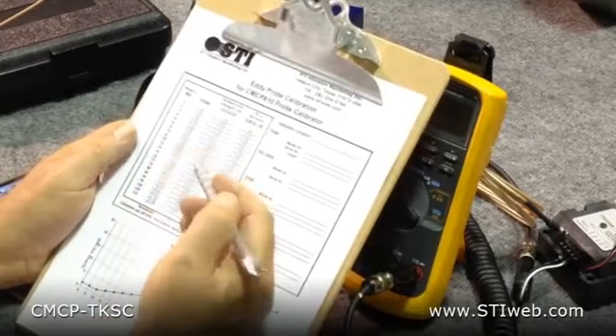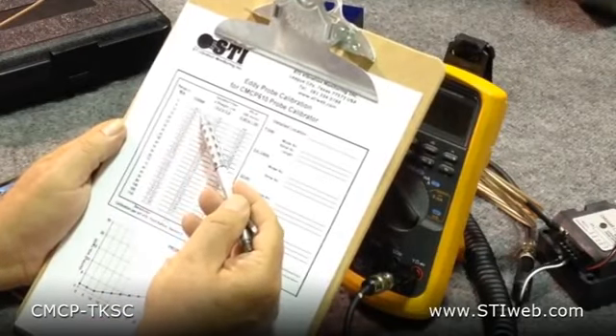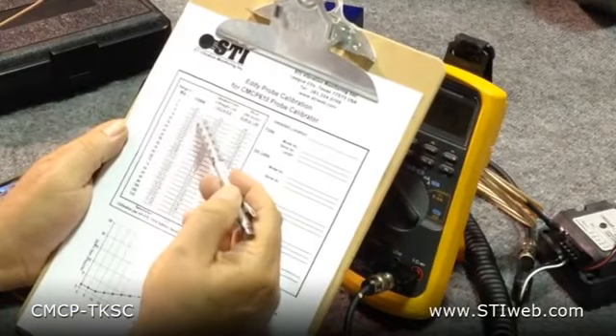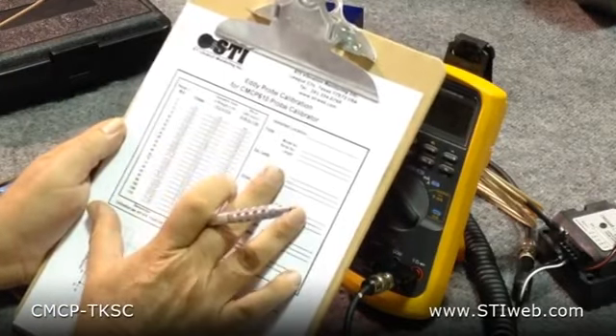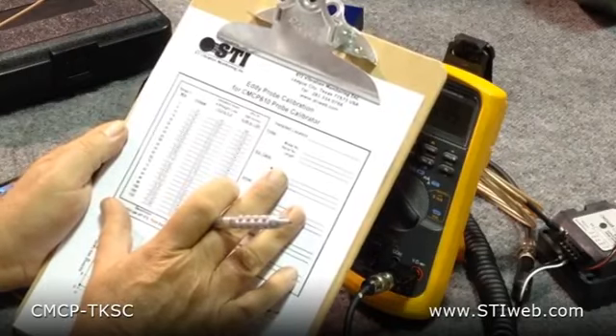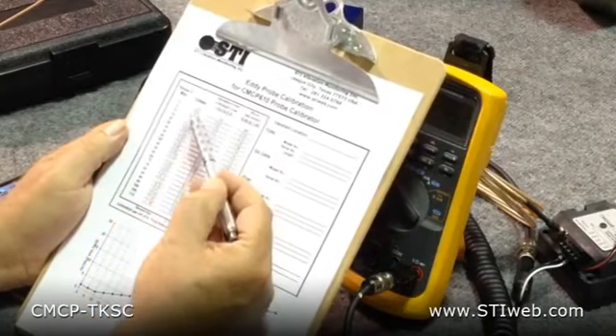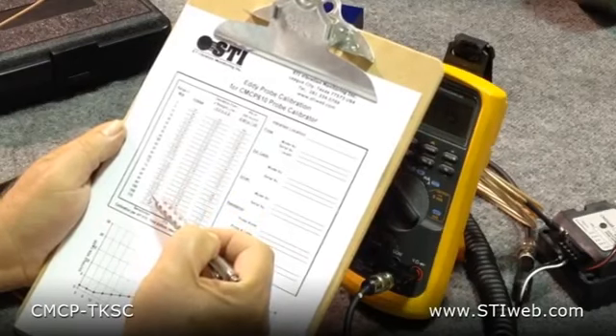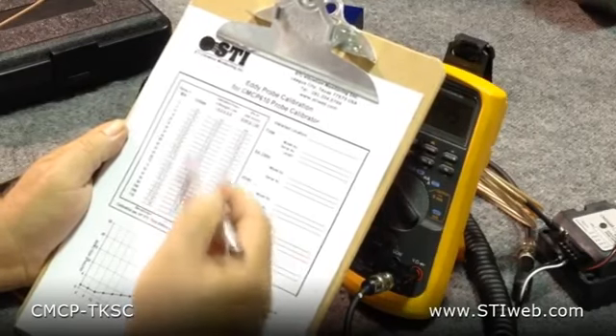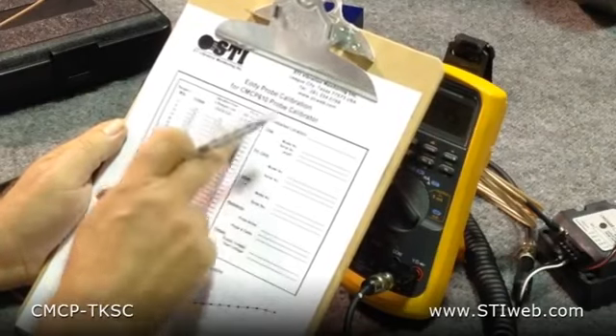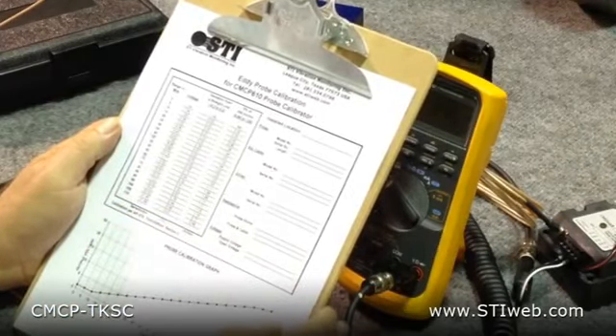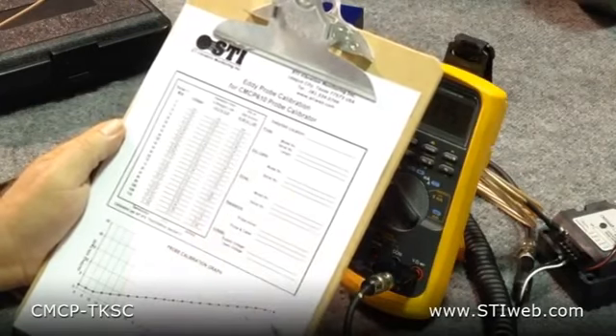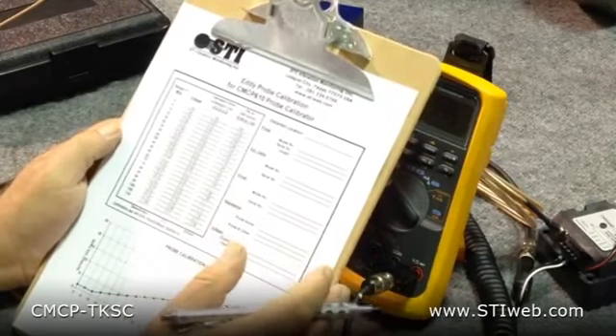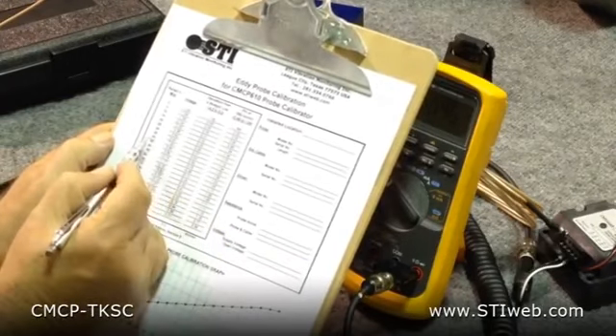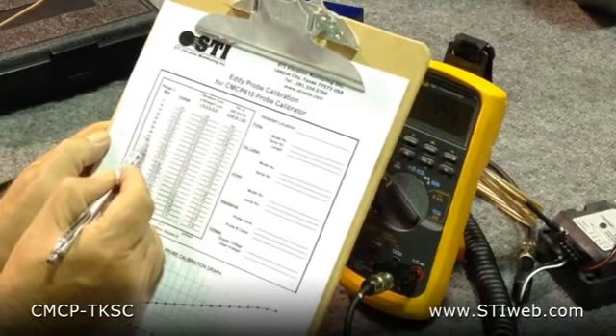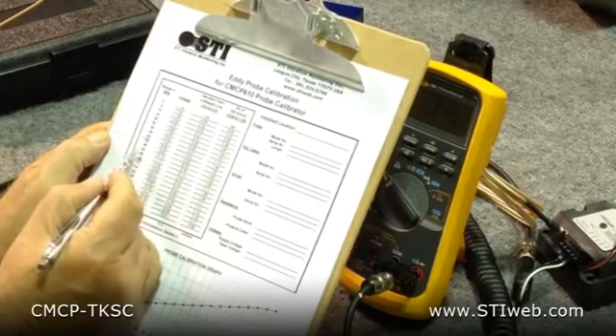What we've done is we've entered all the handwritten voltages we wrote down as we adjusted the dial micrometer. We've entered them on the Excel worksheet that's available to you on stiweb.com under eddy probes. We simply typed in these numbers, which you could have done at the same time as you were taking the values. And the graph will automatically do a curve for you, along with the deviation from what's acceptable for API 670, which is 5%. For what we're trying to do with the shaft calibrator, we determine what our calibration is. Most probes are gapped somewhere between 45 and 65 mils, usually in the 55 or 50 mil category.